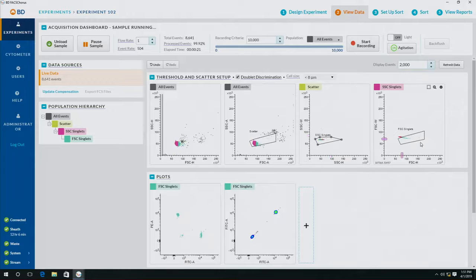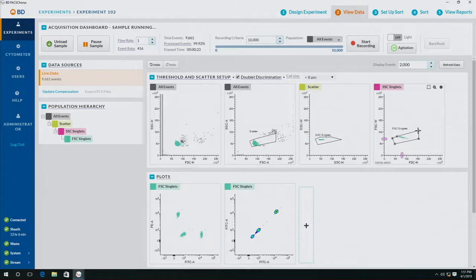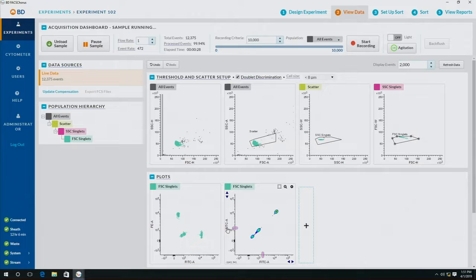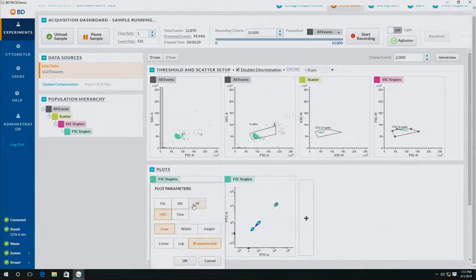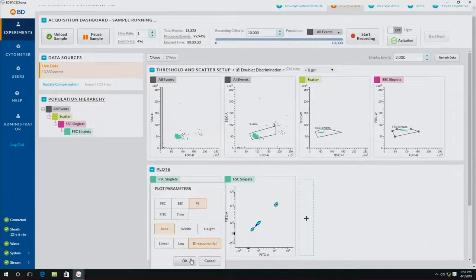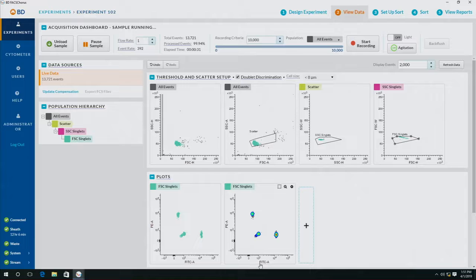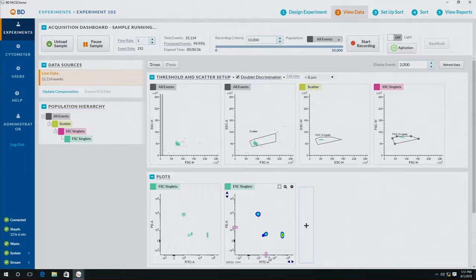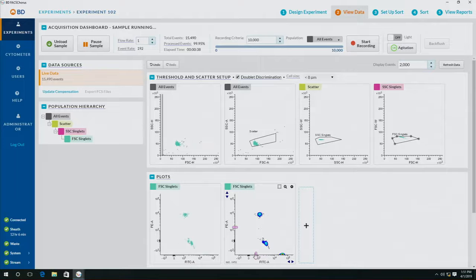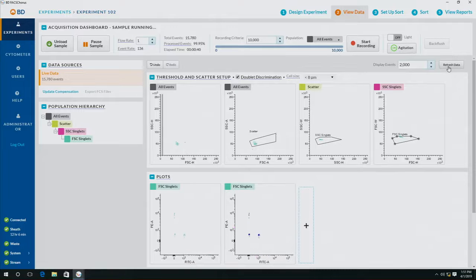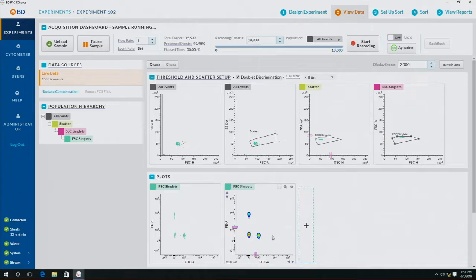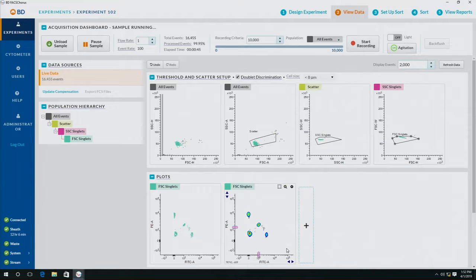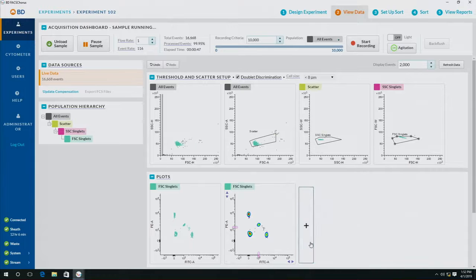I can also use the pink slider on my FITC and PE graph to adjust the different settings. As I'm adjusting the voltages, you can see that FACSChorus, the BD FACSMelody software, is actually recalculating compensation.